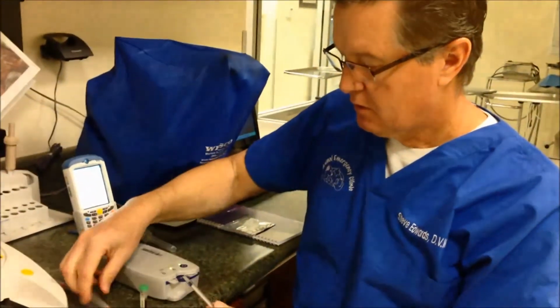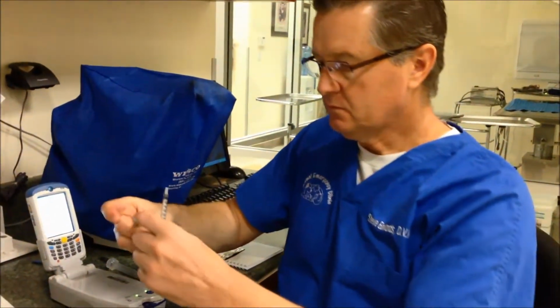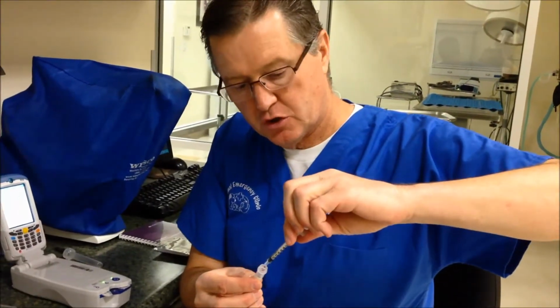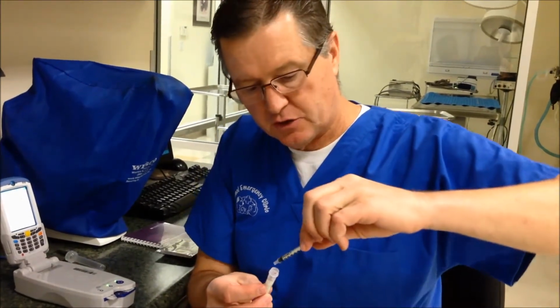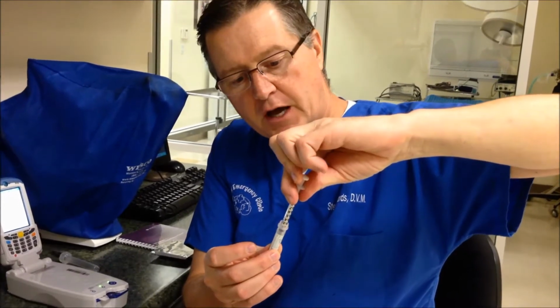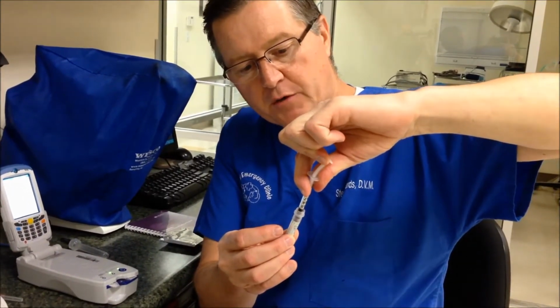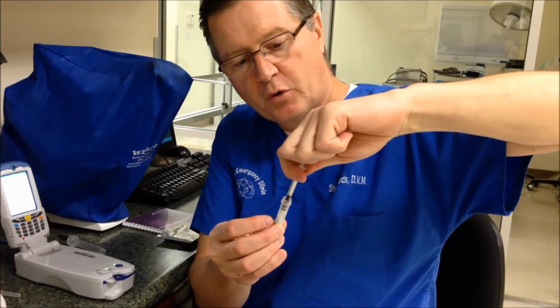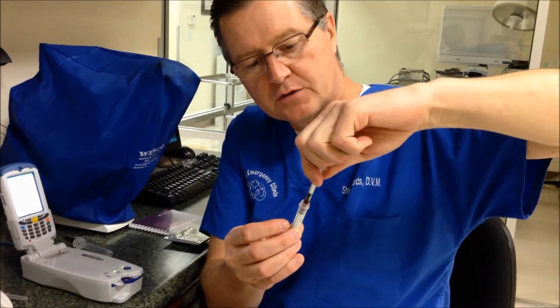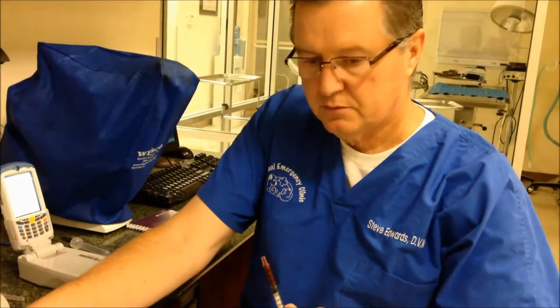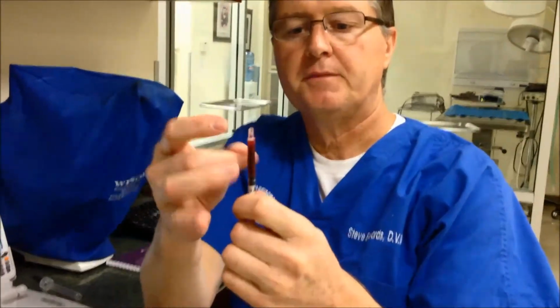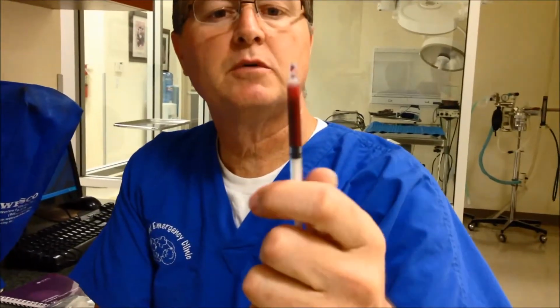So I'm going to gather my sample. We need to have about 0.2 to 0.25 of sample prepared in the syringe to put in the machine. I have found that it only uses about 0.15, but it's good to have a little bit extra. I'm going to use the tuberculin syringe and draw into the syringe well over my required amount. So I'm gonna pull in here a good 0.3 mLs, and then very critical that we not have bubbles. So I'm going to work my bubbles up to the top. Grab it.